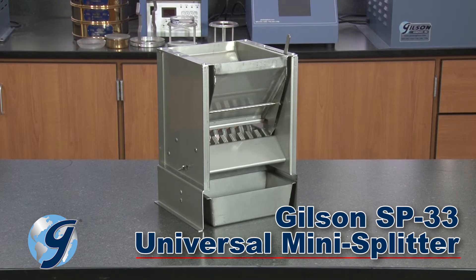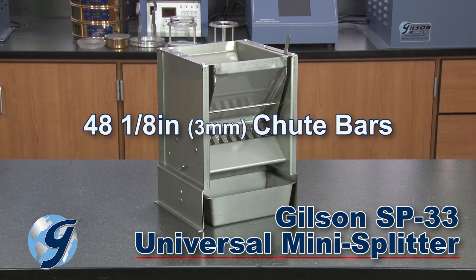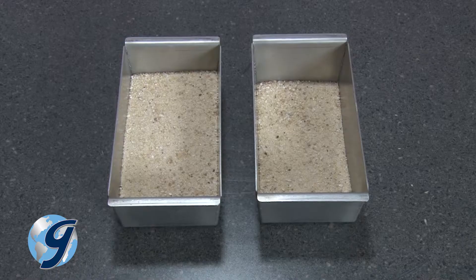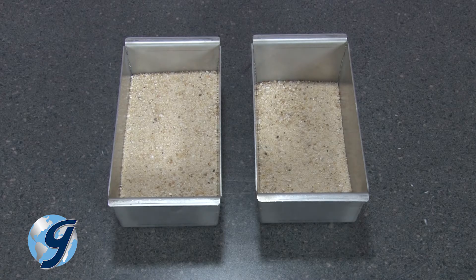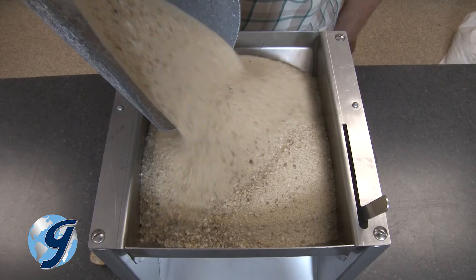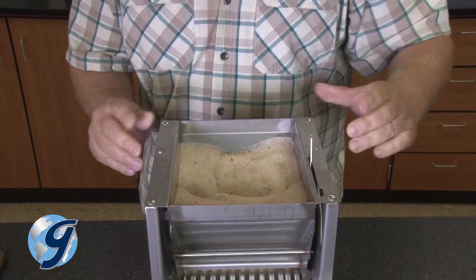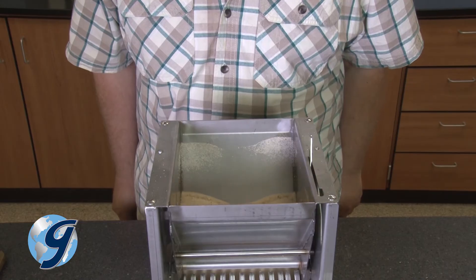The Gilson SP-33 Universal Mini Splitter has 48 one-eighth-inch chute bars at a 60-degree chute angle. The SP-33 has two pans to hold the two halves of the sample following splitting, and a 1.7-liter hopper by which the sample may be fed at a controlled rate into the chutes.